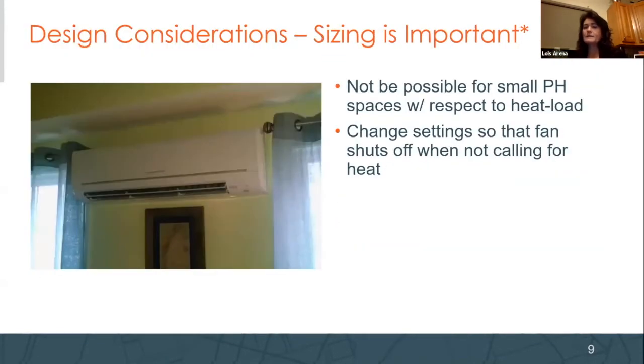So it's not possible for small passive house spaces with respect to heat load. You can't properly size this. A wall mounted head is going to come at a minimum of 4,500 to 6,000 BTUs. The load in a multifamily apartment is probably 500, right? So you're like 10 times oversized. And then you want to change the settings so that the fan shuts off when it's not calling for heat. They come from the factory in fan continuous mode, so even if it's not calling for heat, the fan's going to run on low. You definitely want to make sure that the settings in the unit are set so that your fan is not running when the heat is not needed.